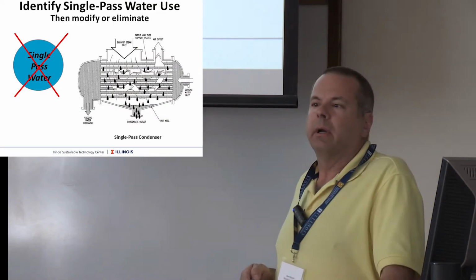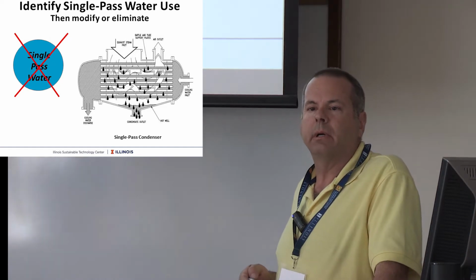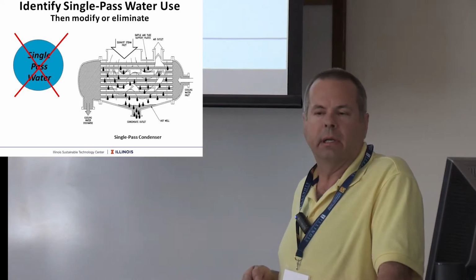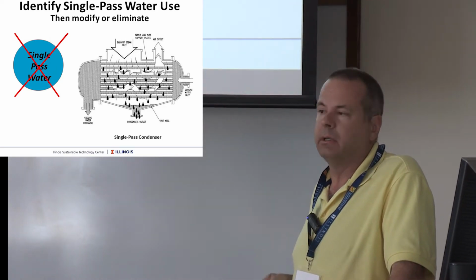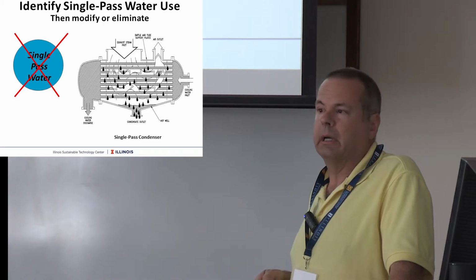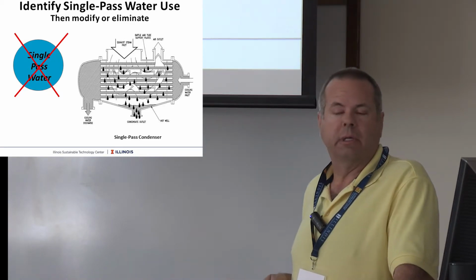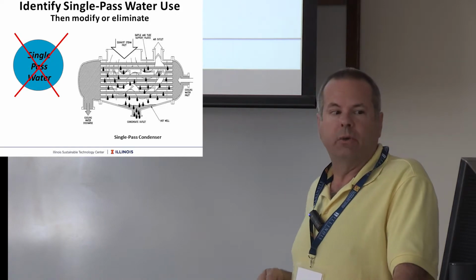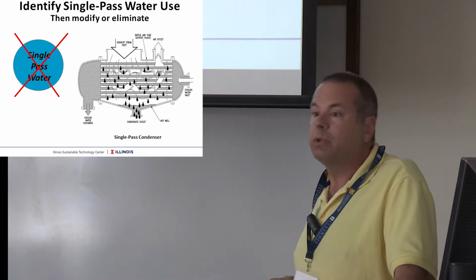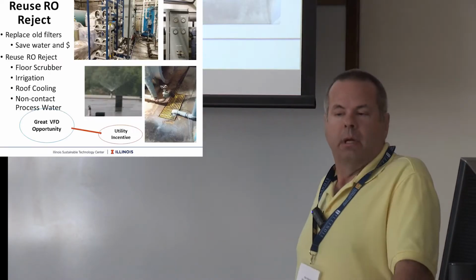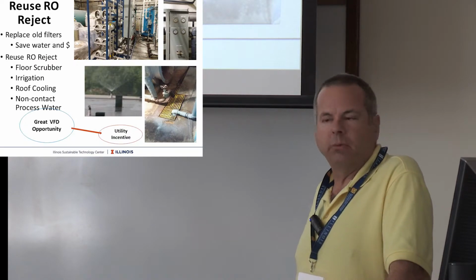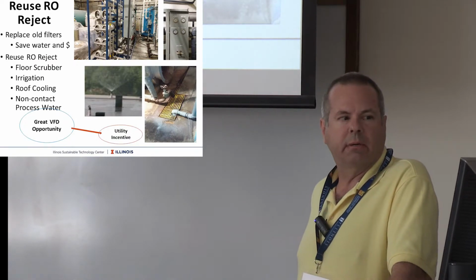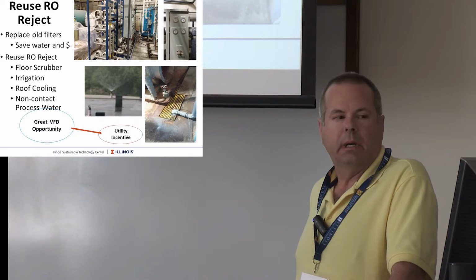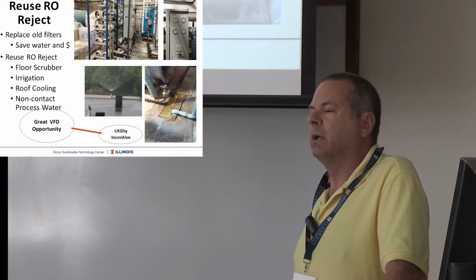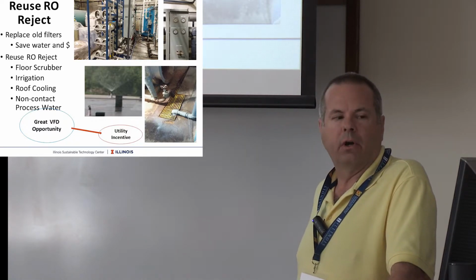Eliminating single-pass water. We still see single-pass water being used, especially in air compressors, water-cooled compressors, hydraulic equipment, and condensers. Rather than using single pass, we recommend some kind of a closed loop system. Also, reuse RO reject water - RO is very expensive water; you reject a lot of water to make one gallon of RO.